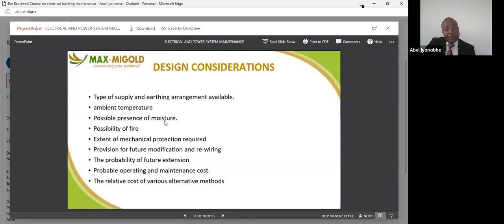Possible presence of moisture is also a factor to consider. Those of us on the island are faced with moisture from the sea, with salt content affecting your installation, causing high resistance that prevents the free flow of electricity at your terminal point. So you need to put this into consideration and make plans for adequate maintenance so that we can get quality supply at all times.